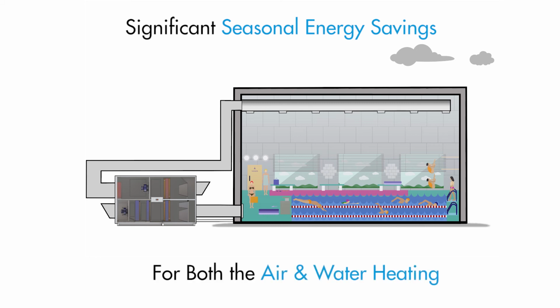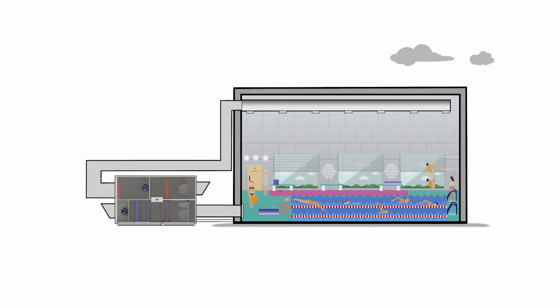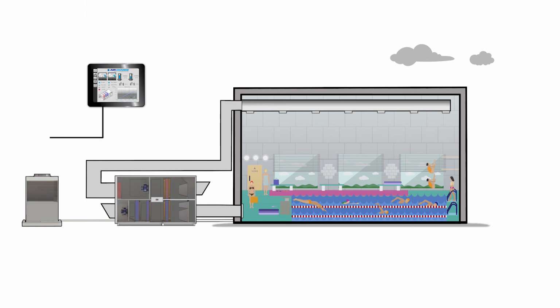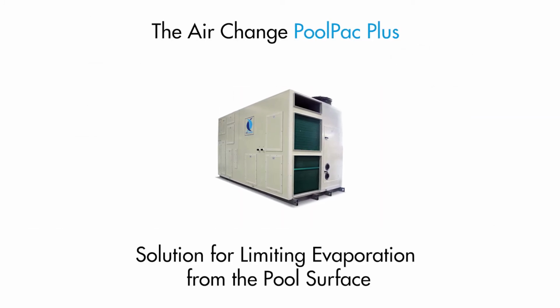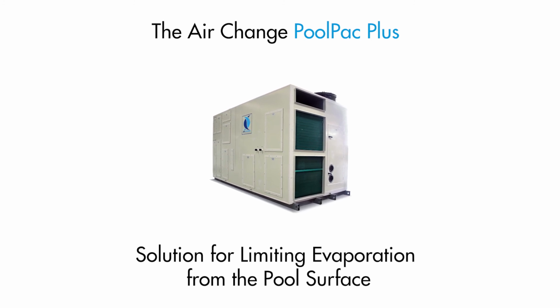Also, the same efficiency boosting principle applies to the pool air heating, where the air and water DX heat pumps can take it in turns to absorb heat from the exhaust air, or absorb it at the same time if needed, where a net efficiency gain will still be present. In some cases, an auxiliary heat pump using outside air will be needed. If so, complex algorithms in the PoolPac Plus's control system determine the most efficient source of heating and allocate heat production accordingly. So now on to the third problem and how the PoolPac Plus can help limit evaporation from the pool surface.